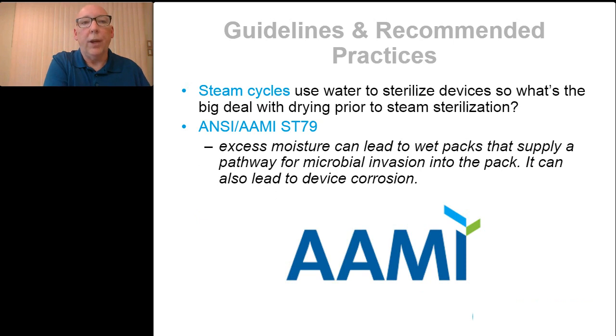Steam sterilization uses water vapor, steam, to sterilize devices. So what's the big deal with drying prior to steam sterilization? Well, even the smallest amount of moisture can affect the quality of the steam. Just as AAMI ST79 mentions, excess moisture can lead to wet packs that supply a pathway for microbial invasion into the pack and can also lead to device corrosion. That's why it's critical that devices are dry even before they go into steam sterilization. You'll see throughout manufacturers' instructions for use, whether for robotic devices or other devices, that they are to be dry prior to steam sterilization. But it goes back to what I said earlier: there haven't been a lot of studies relative to drying, and there haven't been any universal tests. But there are tools and techniques that we can all implement and apply to assure us that the devices we're placing in steam sterilizers are in fact dry. We're going to talk about that a little bit later on.